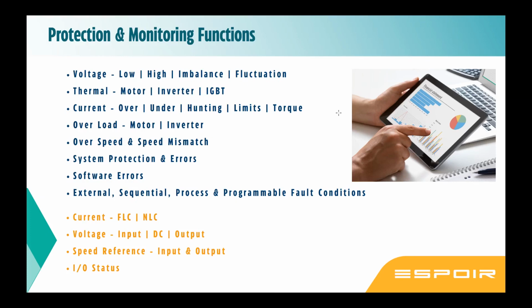Now, if the drawn current is 500 percent, or 5 times the rated current, within 3 seconds, it will consider that probably the motor winding is lost. Motor winding is burned, or there is an output short circuit. If the current is 200 percent for 10 seconds, then it thinks that probably the inverter is overloaded or the cable is open. There are conditions based on current sensing, how much current and for what duration. Based on that, this logic works. And then there are other algorithms inside. It has its intelligence to decide and show you the error code. What could be the possible error could be different from make to make, model to model.